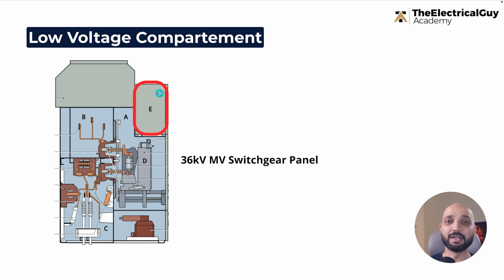Why is that? Because the equipment that we are going to use inside that box cannot accept the high voltage coming from the cables. For example, in this 36 kilovolt panel, you cannot have a 36 kilovolt meter. You cannot have a 36 kilovolt relay. And if you somehow develop that 36 kilovolt relay, it will be huge, right? You need almost this amount of space to accommodate only relays and meters, indication lamps and things like that, right? So to avoid all that, what we do is we step down the voltage and the current with the help of instrument transformers, and then use it in the low voltage compartment, right? So that is the reason why it needs low voltage. It cannot operate on the rated voltage of the system.